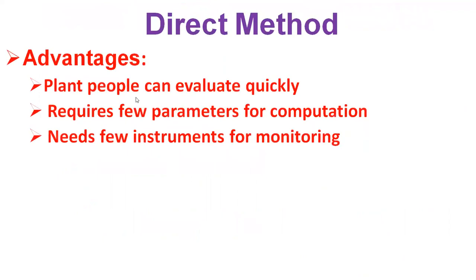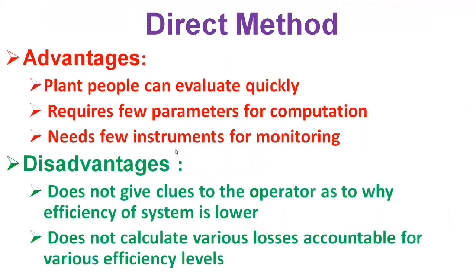The direct method has the advantage that plant personnel can evaluate it quickly. It requires few parameters for computation and needs few instruments for monitoring. The disadvantage of the direct method is that it does not give clues to the operator as to why efficiency is lower, and it does not calculate the various losses accountable for various efficiency levels.